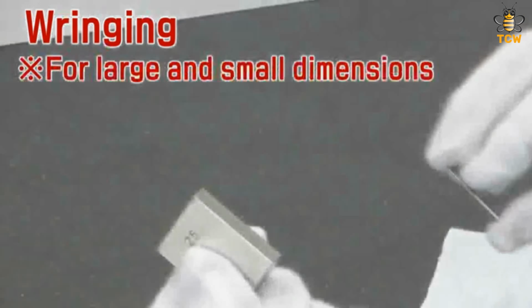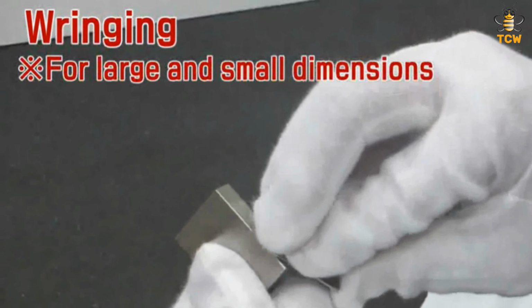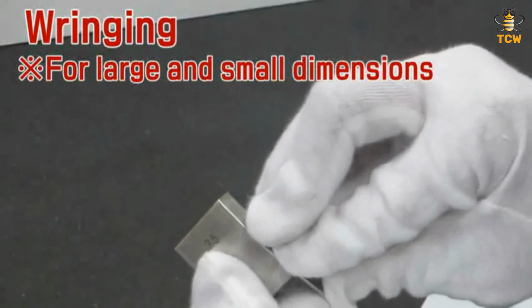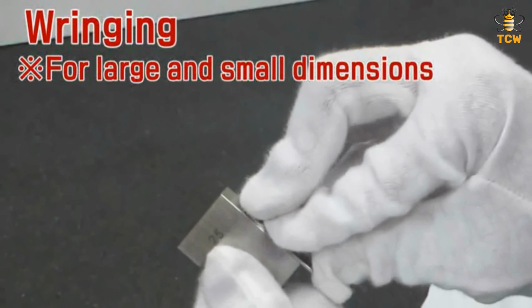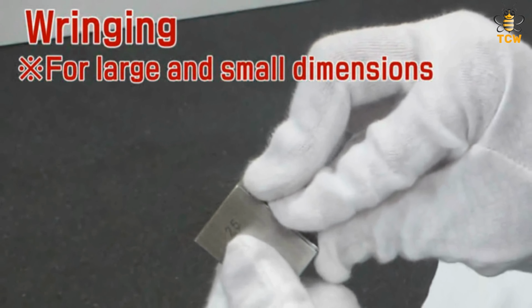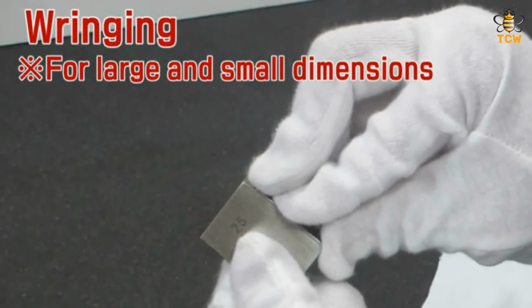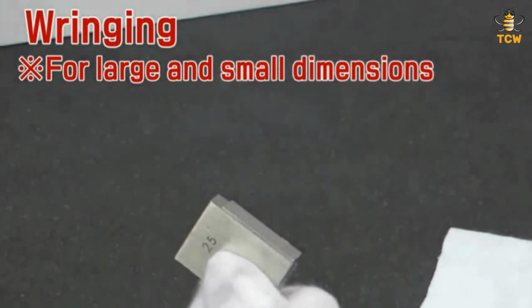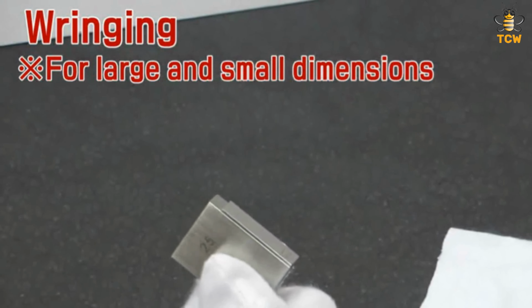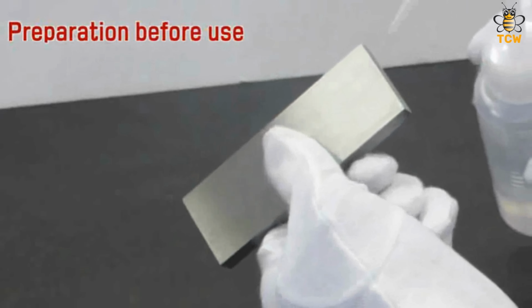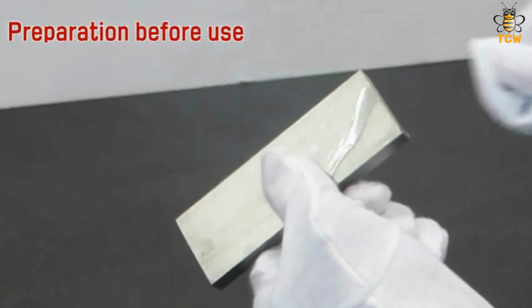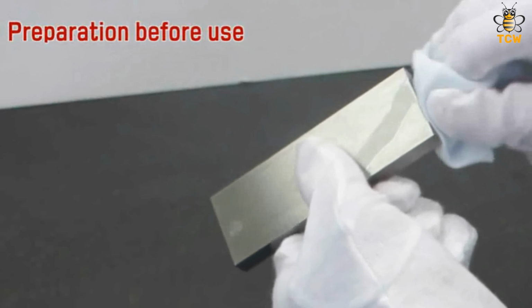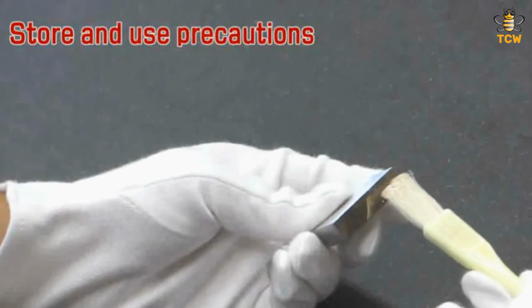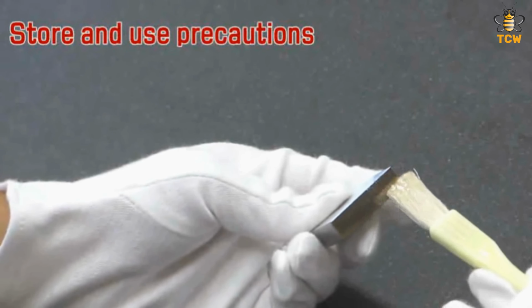To stack thin gauge blocks, attach the thin gauge block face to the other end of the gauge block face. Then push the thin gauge block until both sides of the face are tightly attached. Clean the gauge block face before use. Apply an anti-rust coating after use for storage.